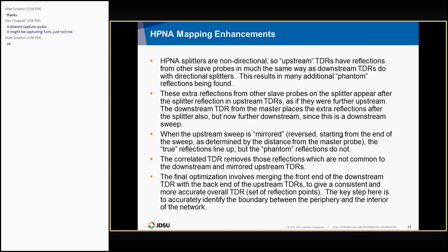Oh, I need to mention this too. That mapping enhancements are, because HPNA splitters are non-directional, so upstream TDRs have reflections from other slave probes in pretty much the same way as a downstream TDR does on a regular network from all the upstream probes. So the extra reflections, just to make a long story short, because I'm running a little short on time here, the extra reflections create a lot of havoc if you don't do something to filter them out.